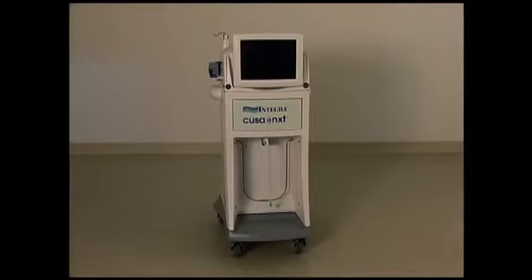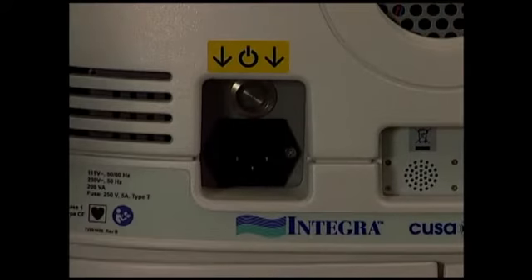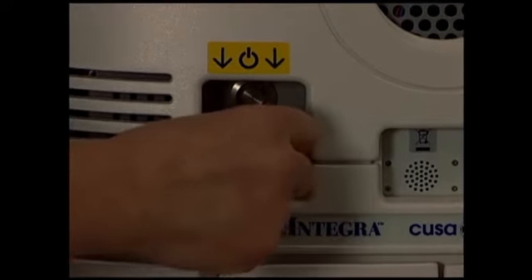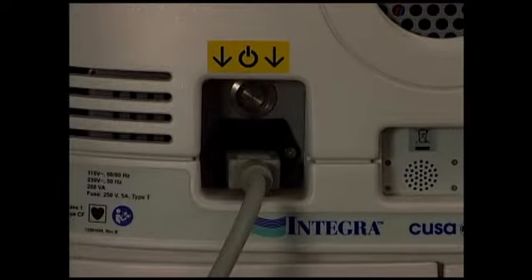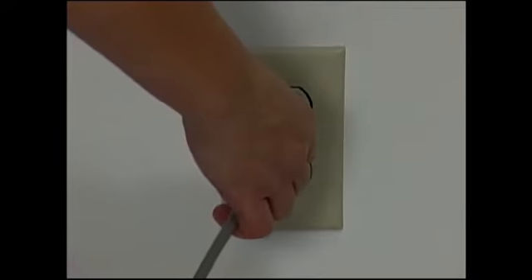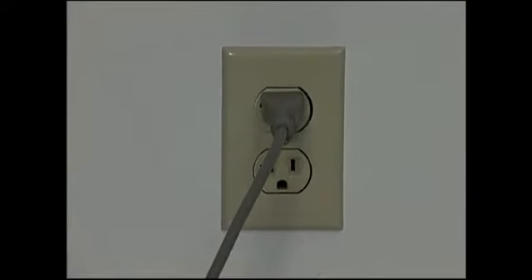The CUSA NXT console sits on top of the service module. If the service module is not used, it should be placed on a wheeled cart. Place the system in a convenient location outside of the sterile field. If the system will be used with wall suction, plug one end of the detachable power cord into the AC power inlet on the rear of the console. Plug the other end of the cord into the wall receptacle.